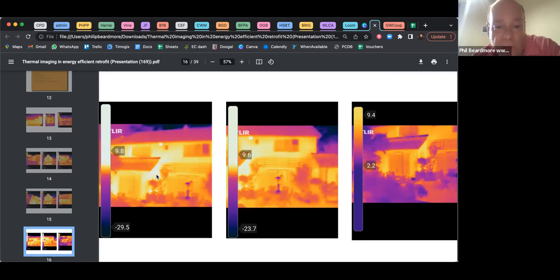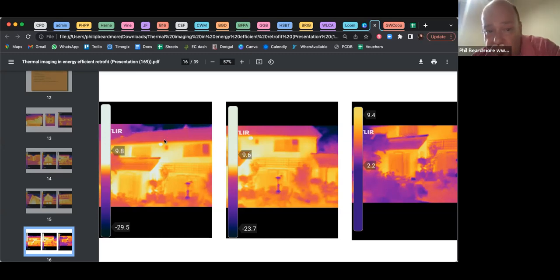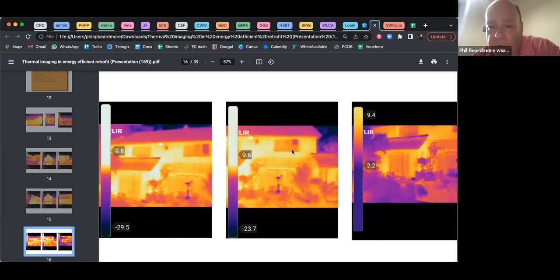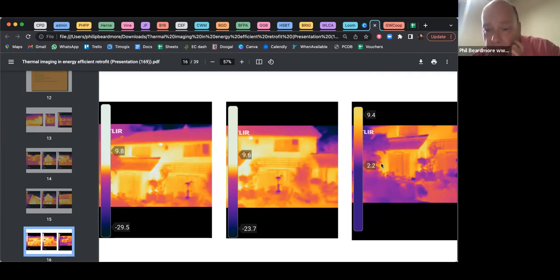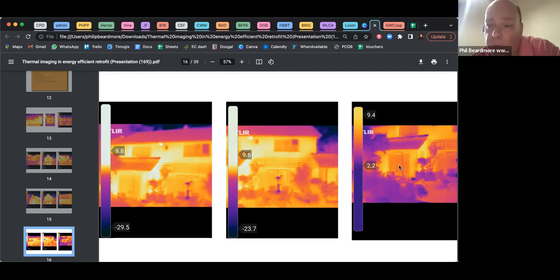This is the house with underperforming cavity wall insulation again. You'll notice the window has changed slightly between images, probably reflecting fluctuation in external temperature — the temperature was going up and down that night. The unheated porch at the back still shows a lot of heat escaping through its external wall, presumably transferred from inside through where walls meet or through the internal door. A porch can contribute to heat loss.